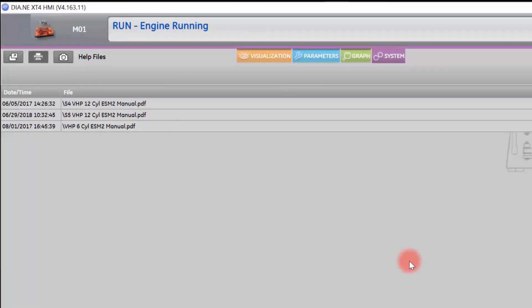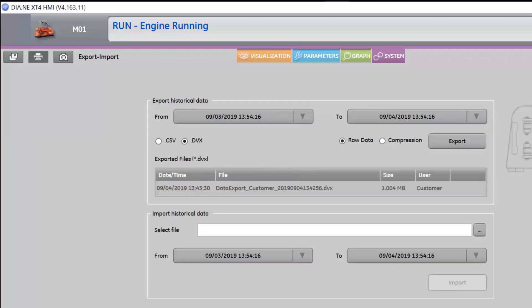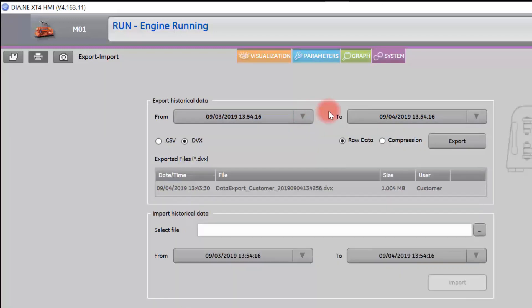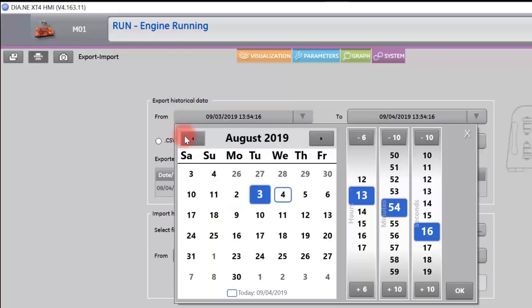In order to export all data from your HMI to a data file, select the System tab on the bottom left-hand side. Select import-export. Select the date range that you want to export. Here I only have selected one day's worth of data to export. If I want to export more, I simply choose the appropriate time and date range. I can either export as raw data or compress the data for a smaller file size. If you have a very long date range, you will select compression.